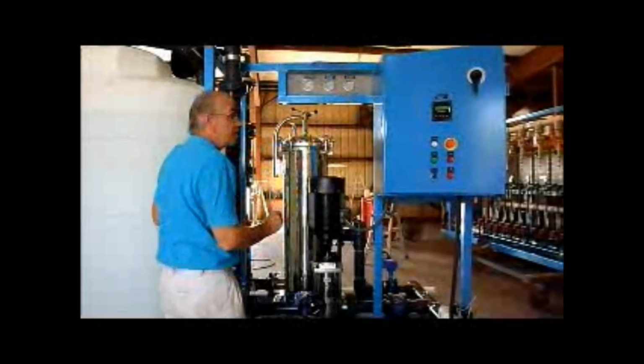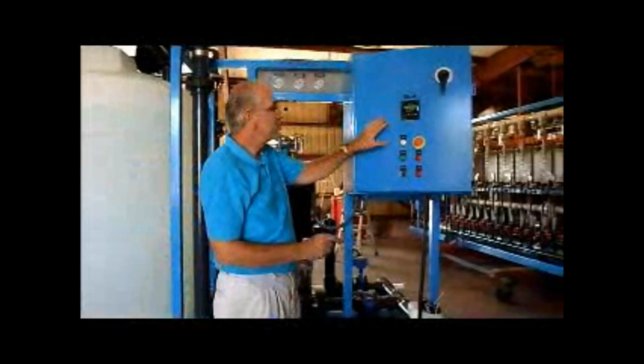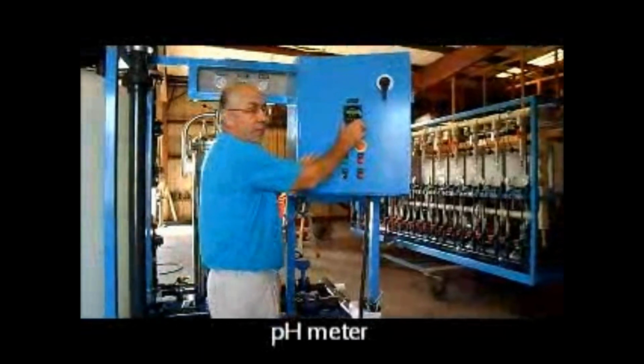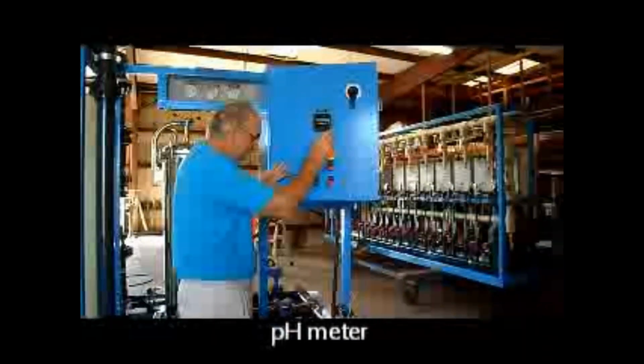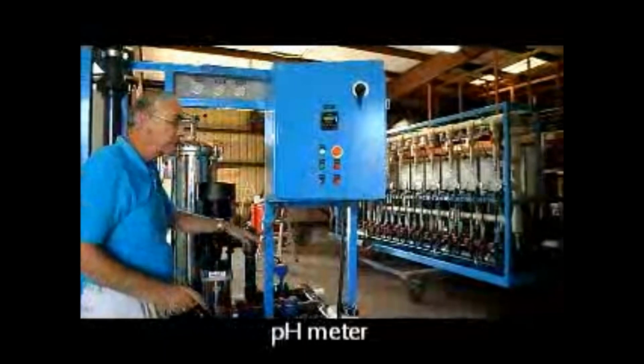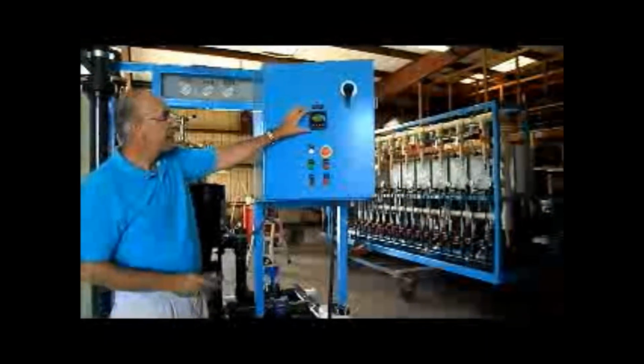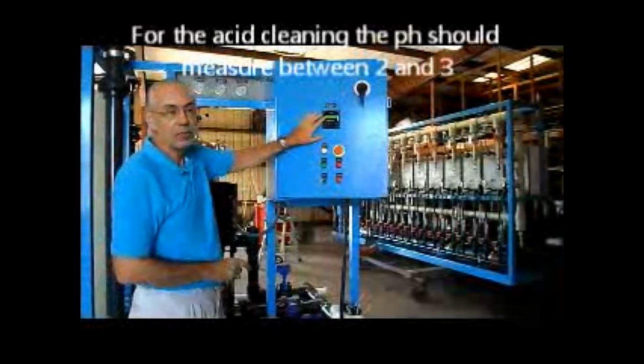Let's talk about the instruments here. You have one instrument on the front panel. This is a pH meter. It measures the pH of the solution flowing through the system. When you're doing an acid cleaning, this pH should measure between 2 and 3.